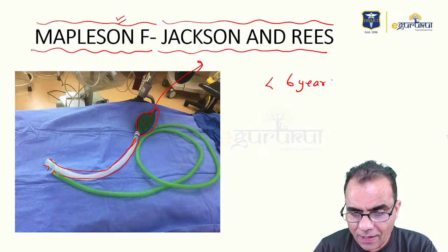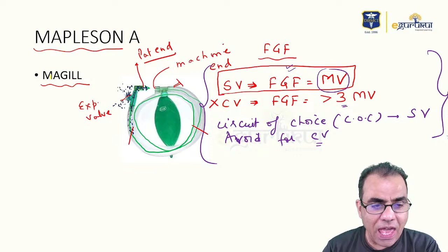So now let's summarize these semi-open circuits. Semi-open circuits were described by Mapleson. As I told you before, in books you may find Mapleson being classified as semi-closed, but that has changed now. Their category is now semi-open, because we have seen that the fresh gas flow requirement in Mapleson circuits is always more than the minute volume. So they are semi-open. Mapleson A, also called the Magill circuit, is the circuit of choice for spontaneous ventilation, and the fresh gas flow required for spontaneous ventilation is equal to the minute volume. It should not be used for controlled ventilation because the fresh gas flow requirement is very high, more than 3 times the minute volume.